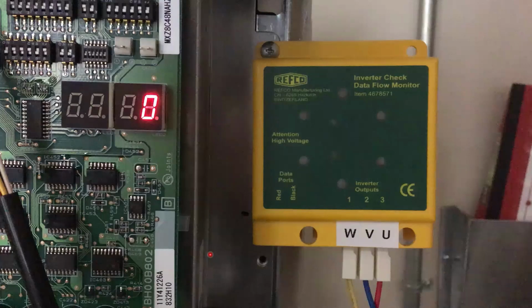When it puts that quick pulse of voltage to the compressor winding, if it sees current draw, it knows there's a short to ground and it will not output any voltage any further. If it passes that test and it does not see a short to ground, then you're going to see the inverter looking for the south pole in the rotor. And I say rotor because our rotors inside of a Mitsubishi inverter-driven compressor is already a magnet. That's why we can turn compressors at various speeds and with as little as 10 volts applied to it.